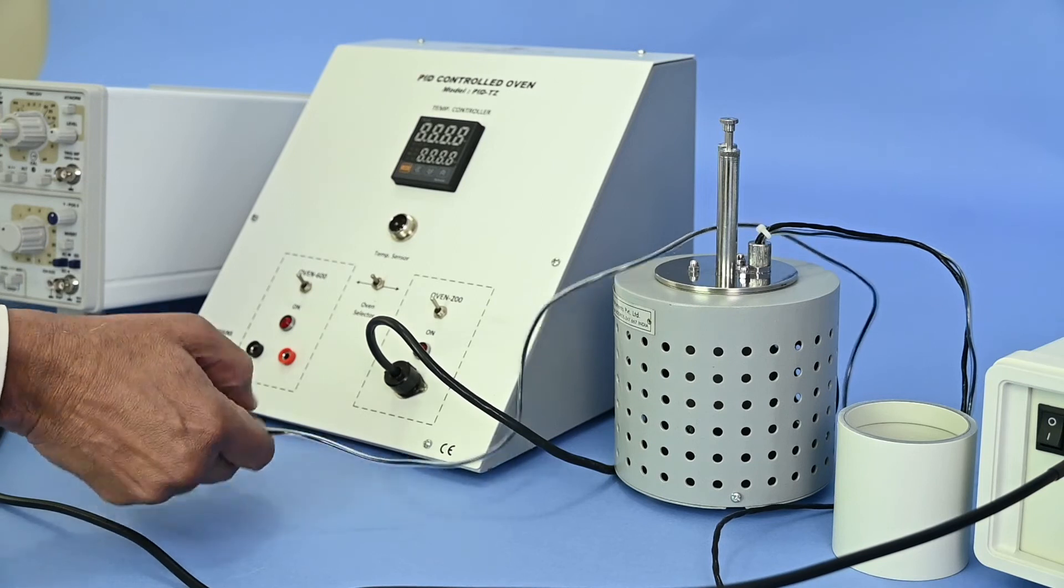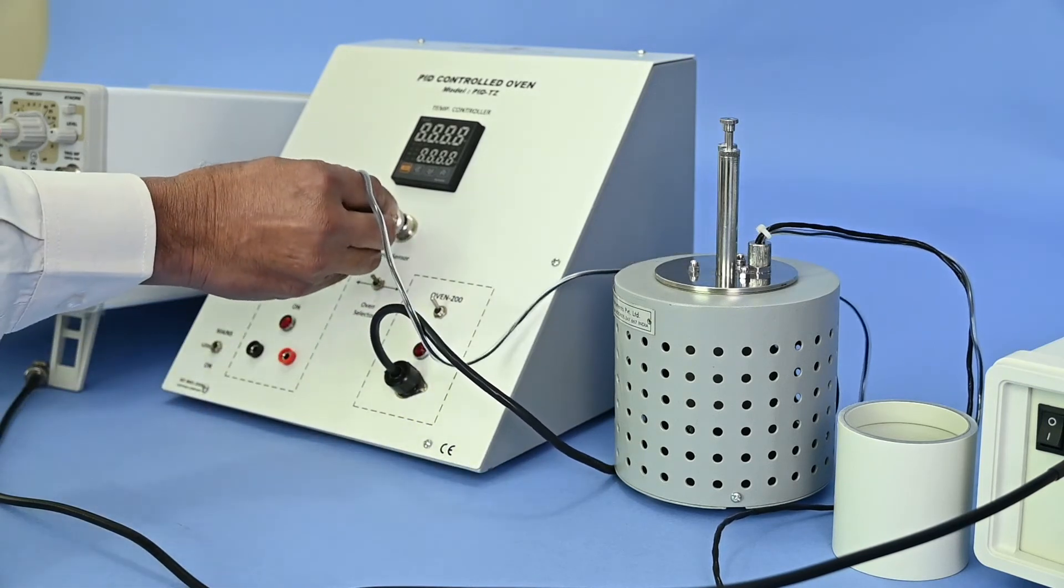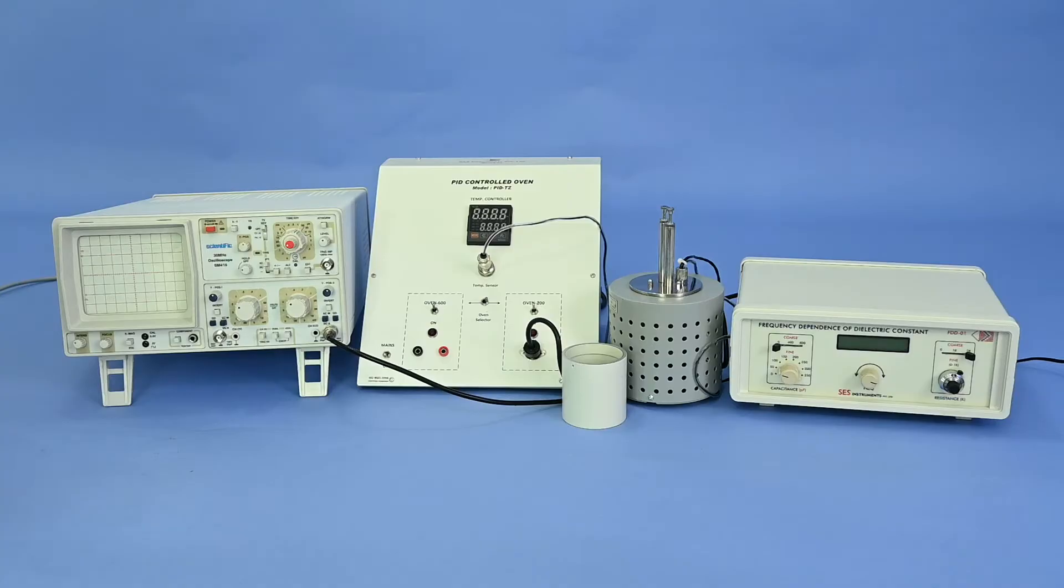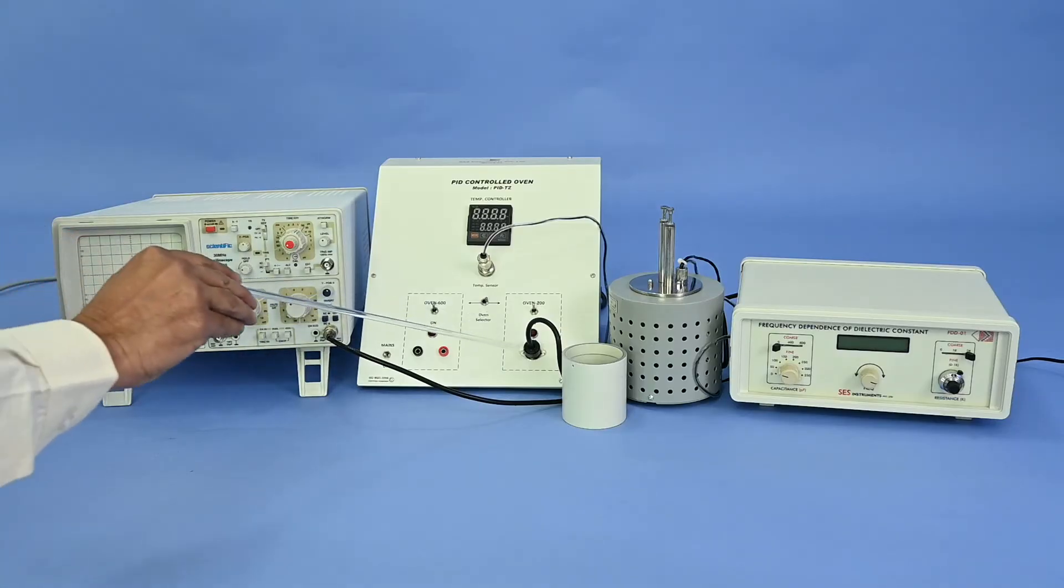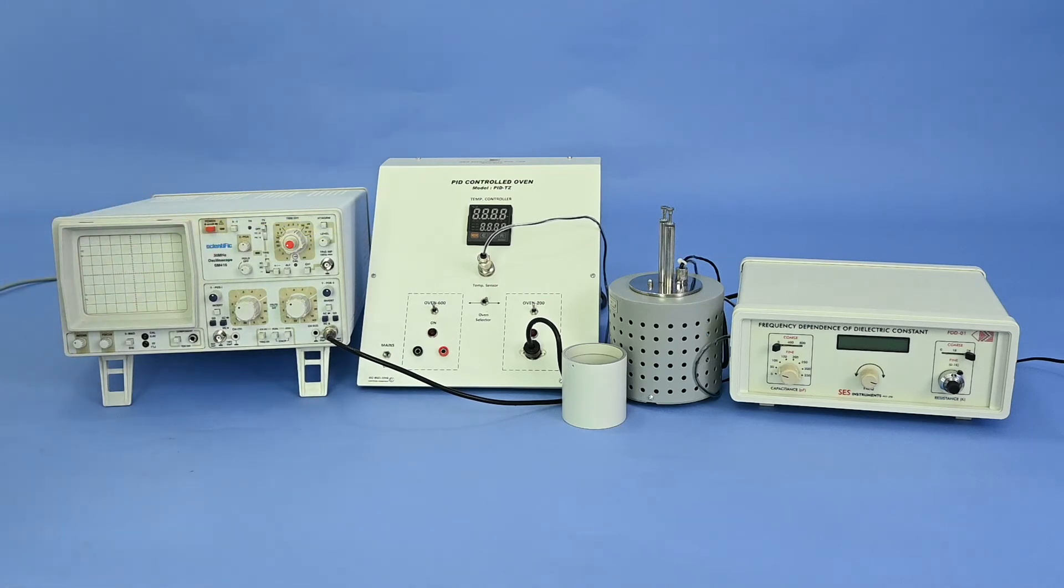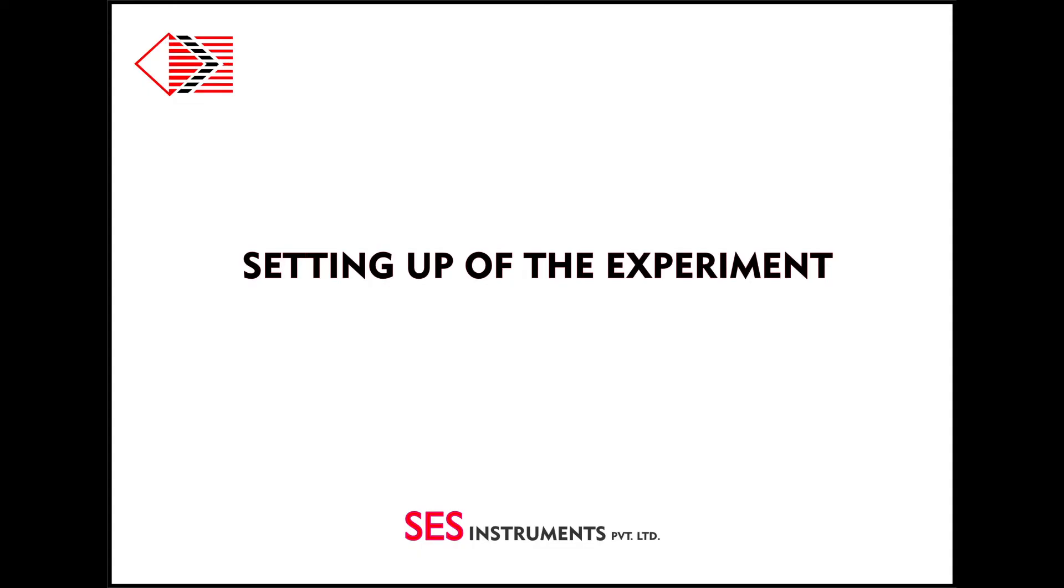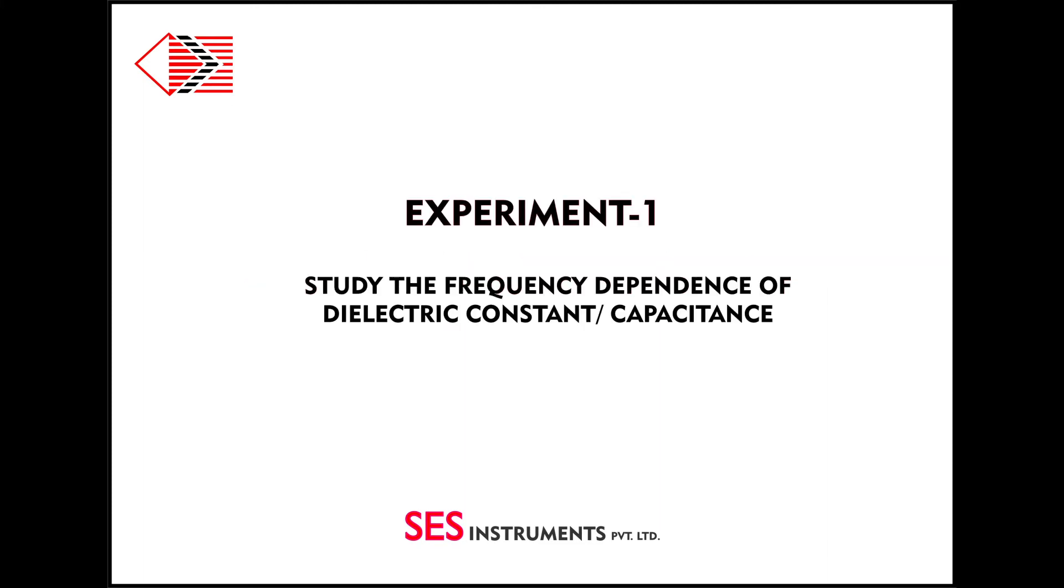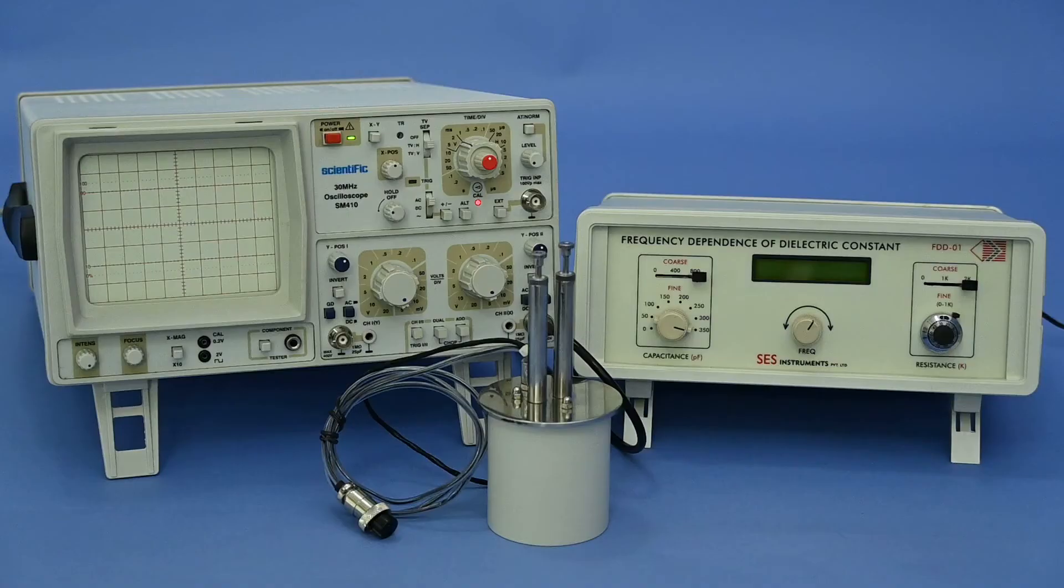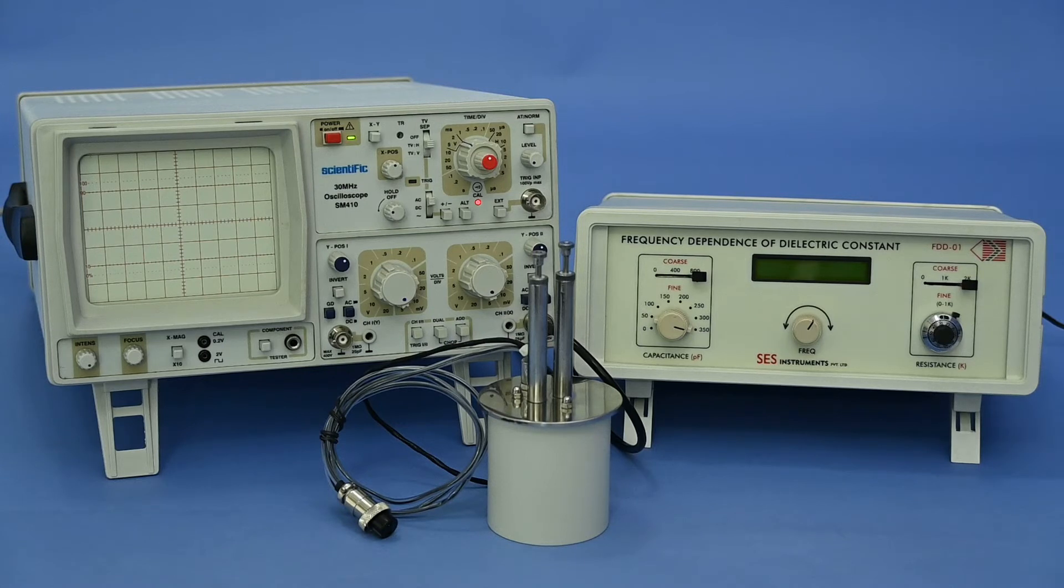Connect 3-pin oven connector to the PID unit socket. Next, 2-pin connector with PID unit. Last two connections are optional. It is only applicable when you have purchased PID-controlled unit with oven. Otherwise, 2-pin temperature connector of this arrangement will remain unconnected to any socket.